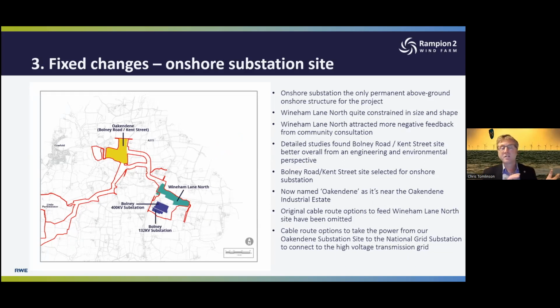We started looking at 7 potential sites for a substation. We need the substation to transform the power up from 150 kilovolts to 400 kilovolts before we connect into the electron motorway, the high voltage transmission grid, which runs broadly from Southampton through to northern Kent and then into London.